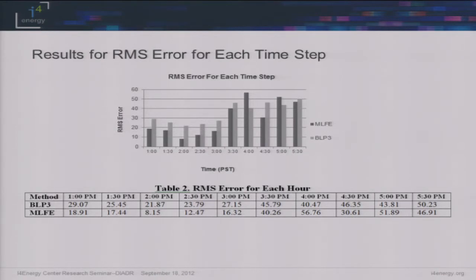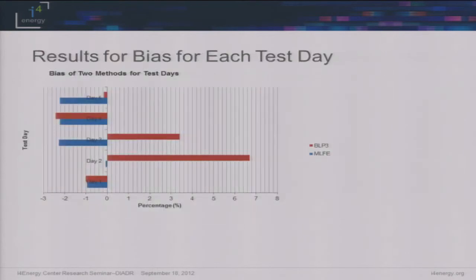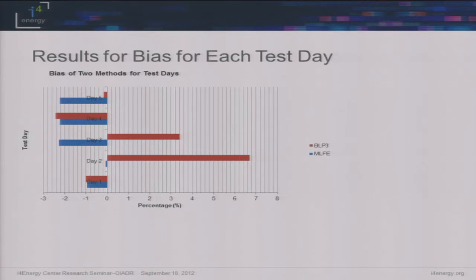I also measured the bias for each of these test days. Our bias was a little shifted — we were under-predicting relative to the actual. But the max we were under was about 2.02%, which is pretty good. It just means that with our model we would actually probably be doing better than we say we're doing, because we're predicting that we'd be using less without any strategy implemented.